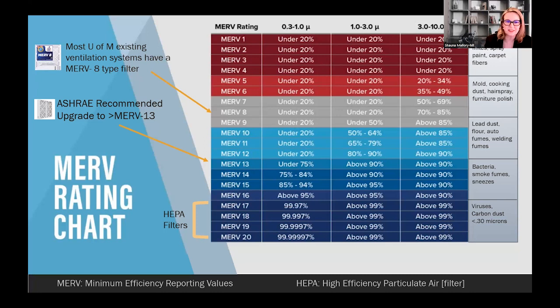So a standard commercial building tends to have a MERV 8, but since the pandemic, ASHRAE, the American Society of Heating, Refrigerating and Air-Conditioning Engineers, has recommended that we go to MERV 13 or greater, which can start to filter out bacteria, smoke fumes, and sneezes. And of course, if we are in a healthcare setting where we have a high number of people with known viruses and flu and so forth, then we are looking at MERV 17 through 20, which, you can see in the left-hand column, can filter out particles 0.3 microns and under 99% of the time, which is extraordinary.